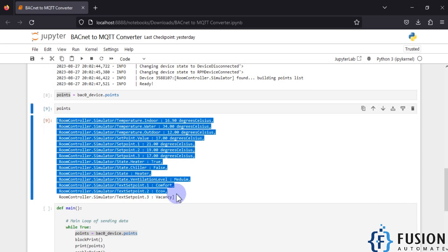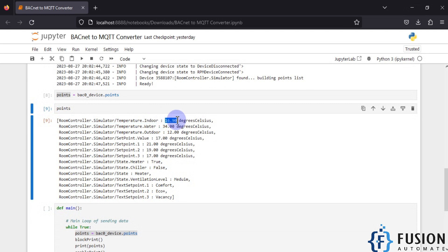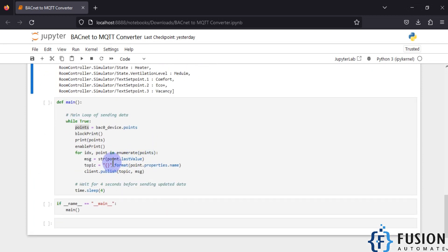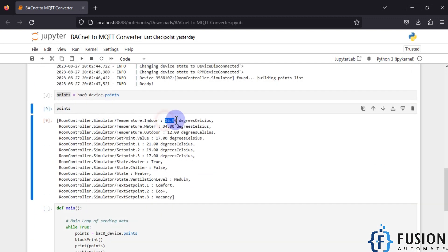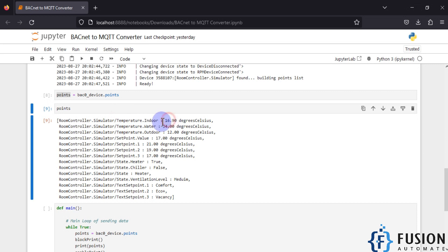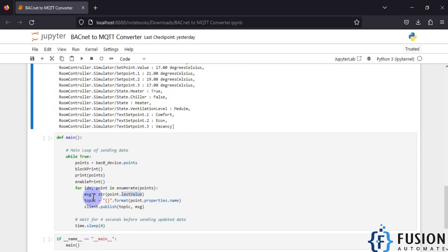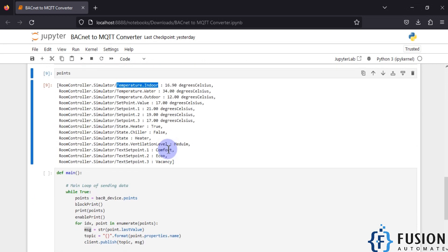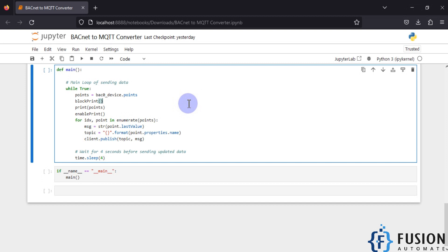You can see here is a list — for each point we have a value and units. This point will get the list of points and the present value of those points. point.lastValue is the last value, and properties.name gives names like temperature.indoor and temperature.water. The value goes as the MQTT message, and the property name goes as the MQTT topic.